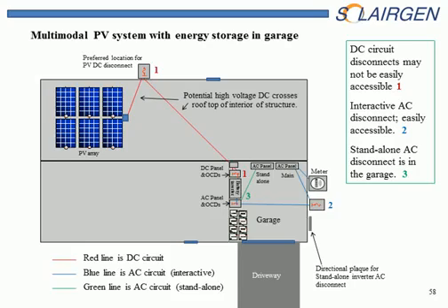So here again, hopefully there's plenty of labeling, adequate plaques indicating where everything is, so you know where those DC conductors are running, because that's the only potential in there that's serious. The batteries are a potential. They're not as critical. They're not as high voltage. The likelihood of flooding them and shorting them out is not extreme. But that high voltage conduit, you want to make sure that you're not cutting into it or creating another fire hazard by breaking it or something.